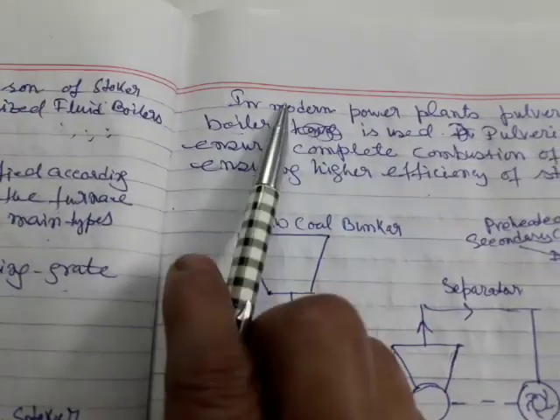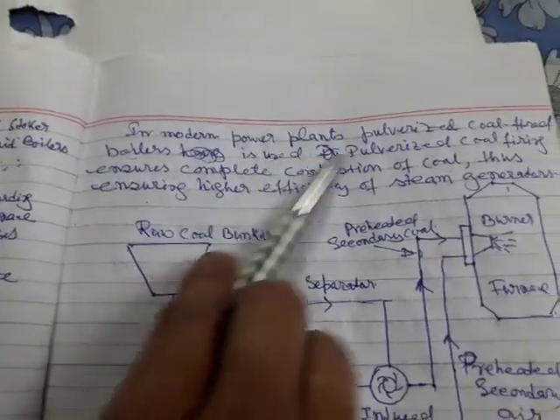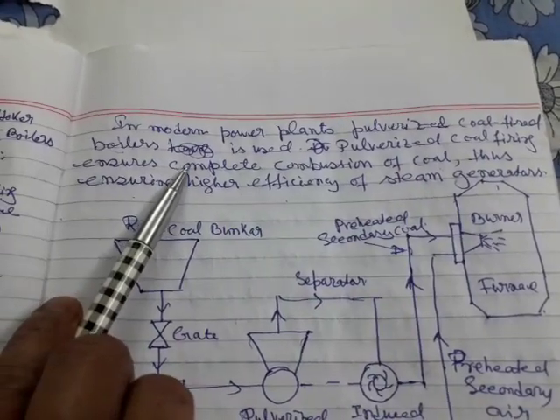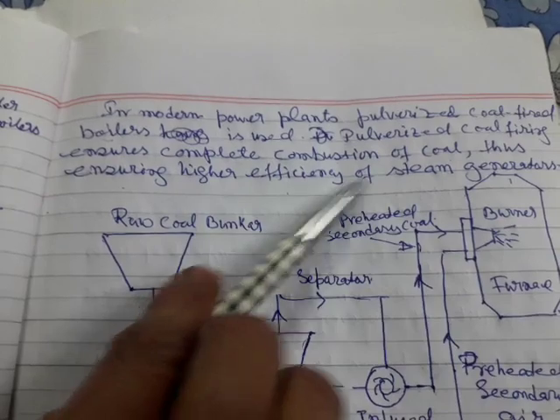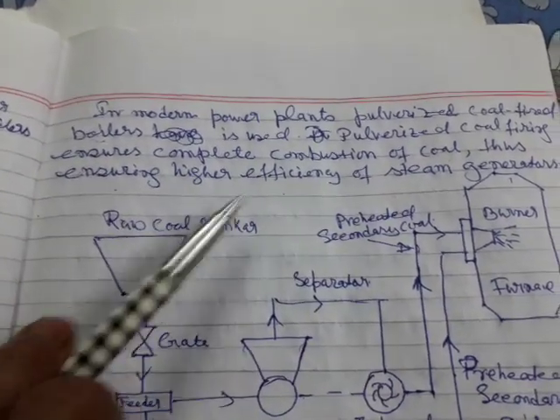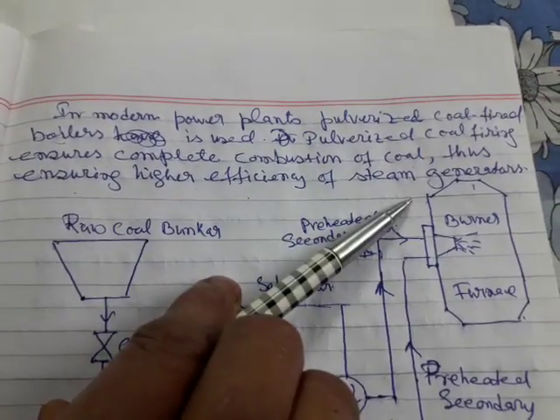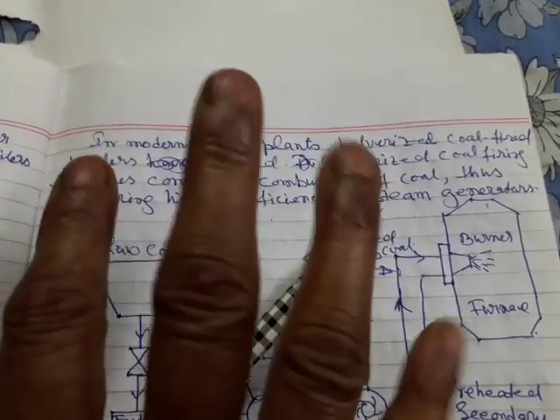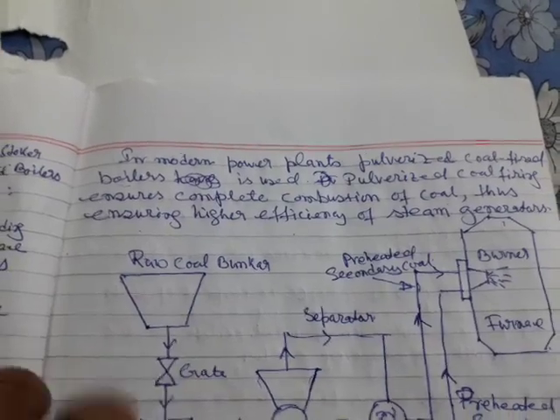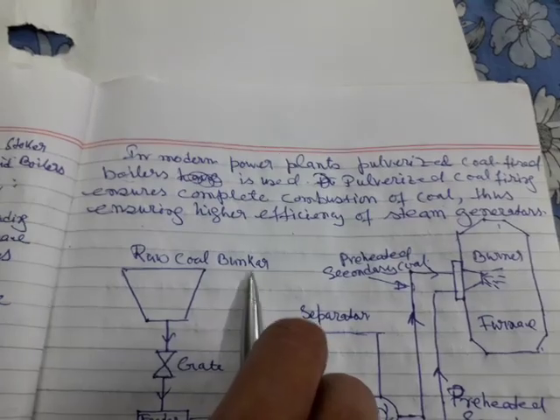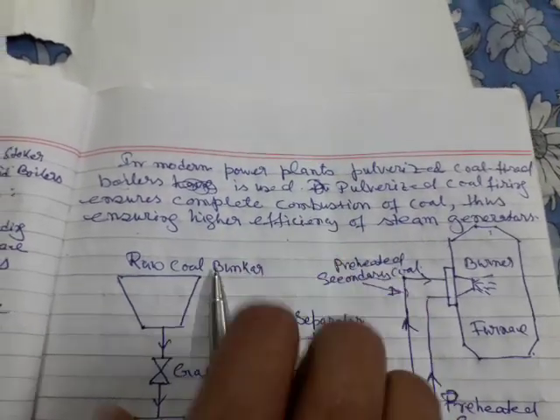In modern power plants, pulverized coal fired boilers are used. Pulverized coal firing ensures complete combustion of coal, thus ensuring higher efficiency of steam generation. When coal is pulverized, the surface area of the coal is remarkably increased, so we can get a greater amount of heat from the same amount of coal.